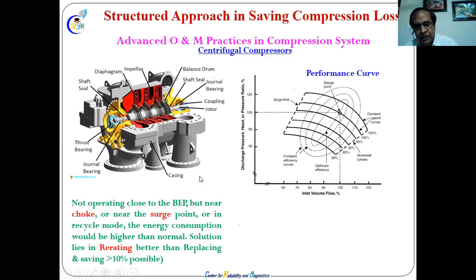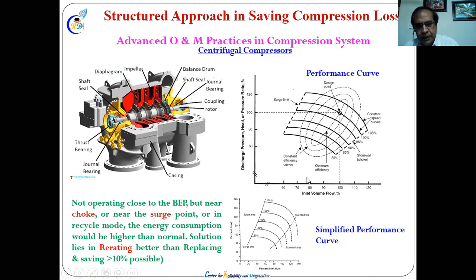I will not go into detail on this because there is no time now. Not operating close to the BEP is a main problem. Operating near the surge point is something we have to avoid. That's why derating of the compressor is the generally common procedure. It is a more simplified way.